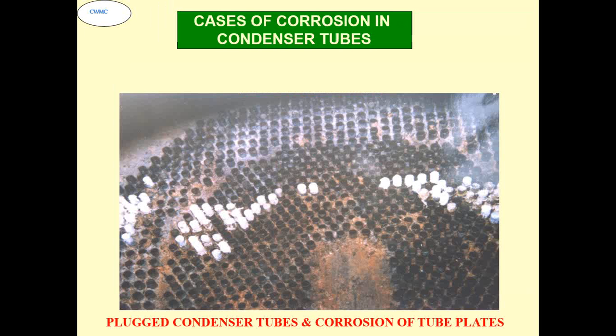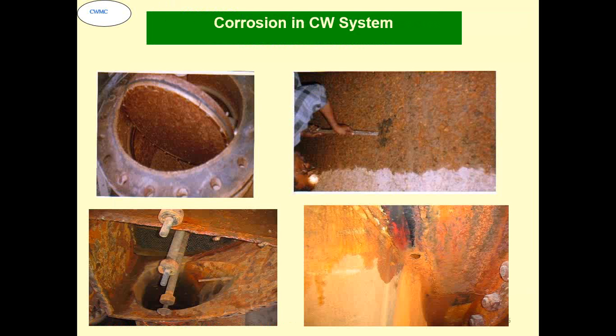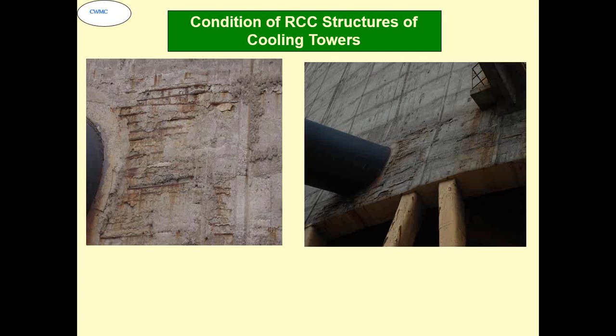Typical condenser tube plugging and condenser corrosion problem. Typical corrosion in the CW duct, walls, condenser water boxes. What you see here is a 40 mm thick plate which was punctured because of the seawater, and there is no coating, no further protection that has been provided. Even in RCC structure, there is severe corrosion, and because of that the reinforcement bars start corroding, especially in the coastal region. Because of the chloride and other things, they start corroding, and once they start corroding they expand, the concrete falls, and the structure becomes dangerous.